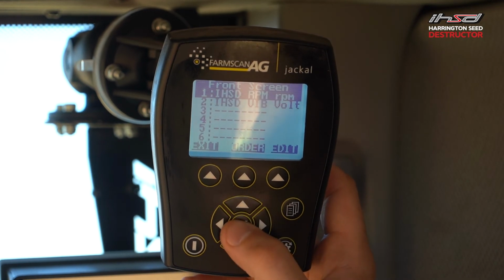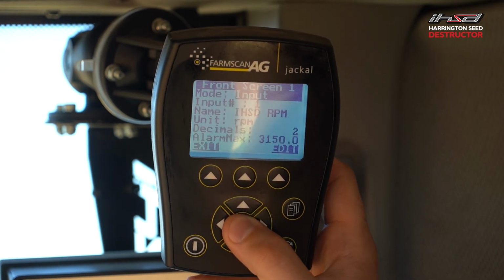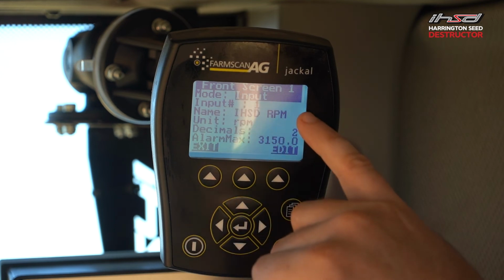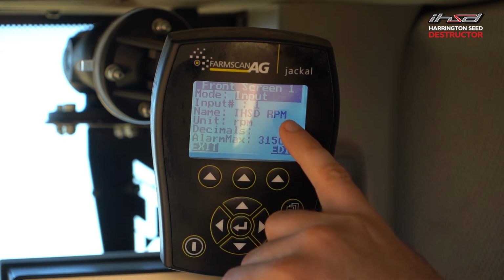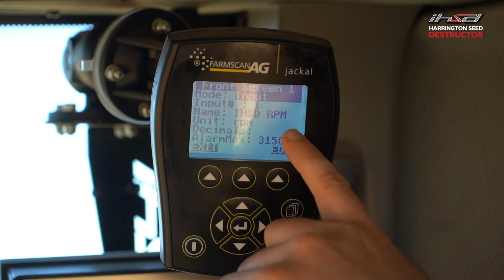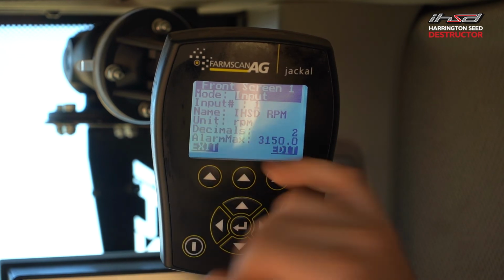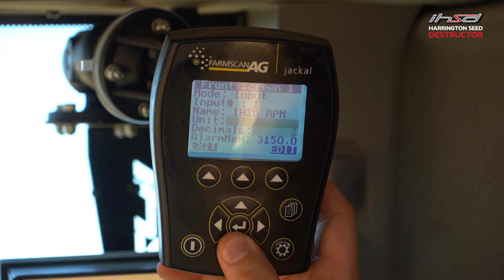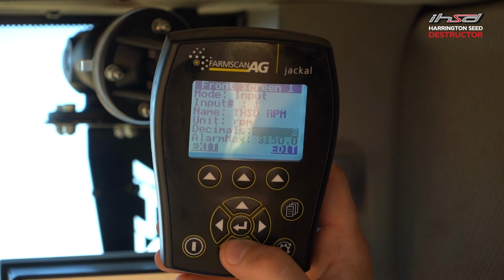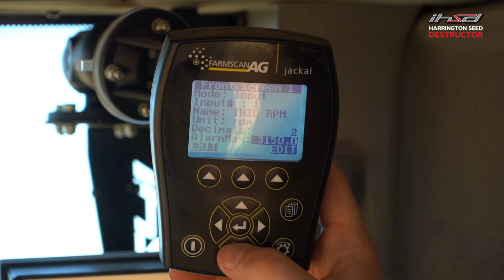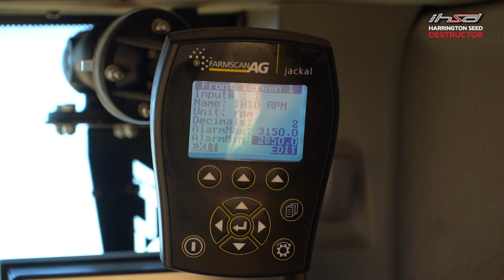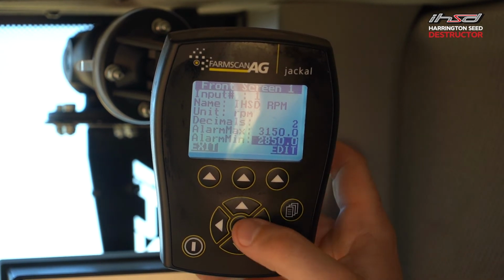Number 1 should be iHSD RPM. The mode should be input, and input should be number 1. We call it iHSD RPM, and the unit should be RPM. Decimals, we normally set at 2, and then alarm max should be 3,150 RPM. Alarm min should be 2,850 RPM.